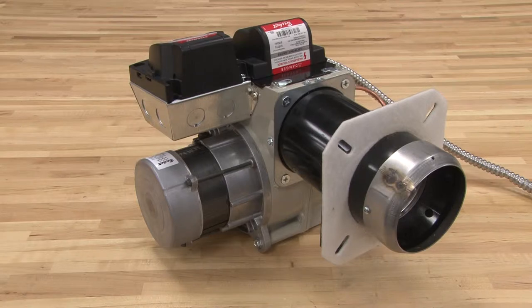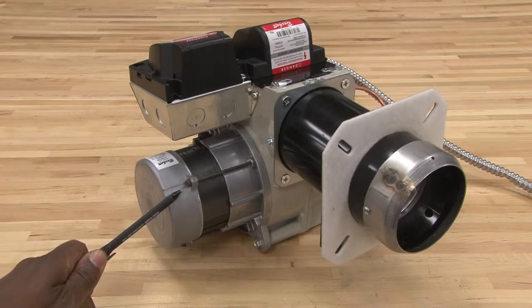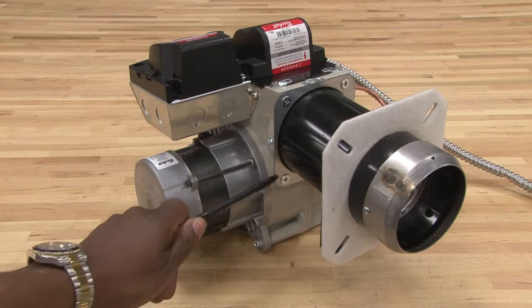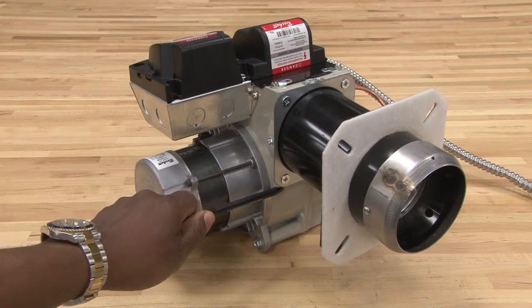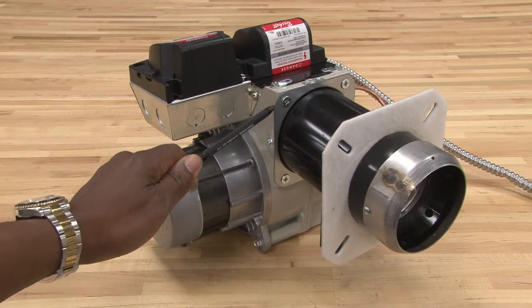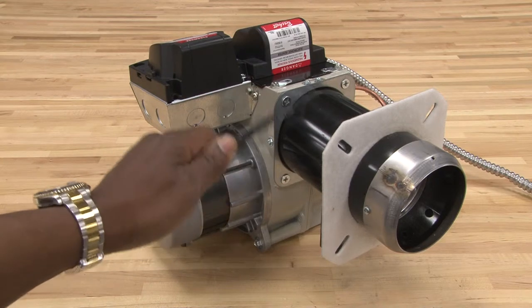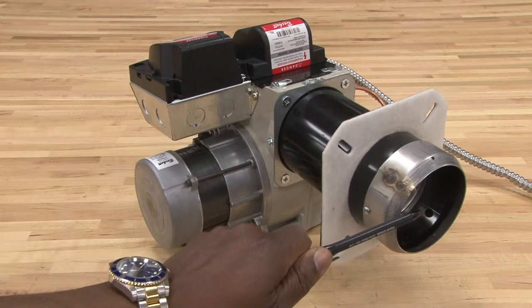This is a burner assembly of an oil furnace. The components on the left side form the blower section. This is the blower motor. Inside the blower motor assembly is a blower wheel which will move air through the burner assembly into the combustion chamber, through the gun, and out through the front where the oil will be sprayed from the nozzle.